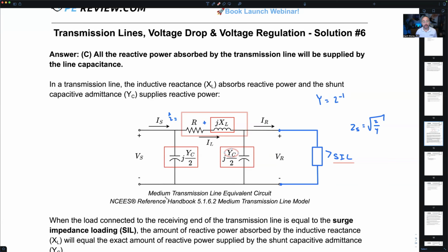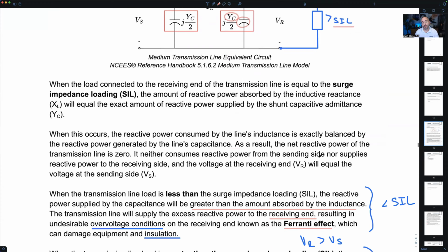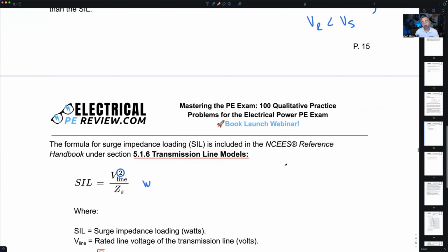When we use the medium transmission line model, what we call the pi model, we take this value, the shunt admittance, we divide it in half, we stick half of it on the sending side, we stick the other half on the receiving side. We distribute it half on the front, half on the back. But in the formula, we're using the total amount. If we can calculate the surge impedance, then we can calculate the surge impedance loading.